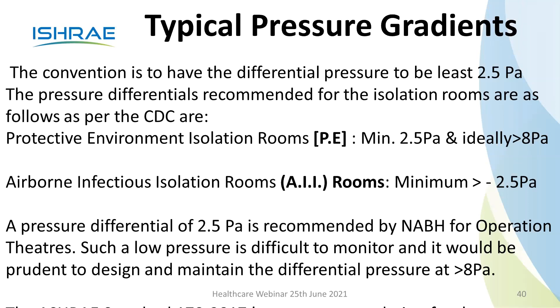A pressure differential of 2.5 pascals is recommended by NABH for operation theaters also, but such low differential pressures are difficult to monitor. So when you're a designer, you better design at something like 8 pascals, so that you are not getting into any problems with the measuring instrument. You don't know it is showing 2.5, but because of the error in the instrument, you might actually not be on the positive side when you're trying for positive 2.5, or the other way around. So if you want to be clear that you're not entering into the other zone, better keep it far away from 2.5. Keep it at something like 8 pascals.